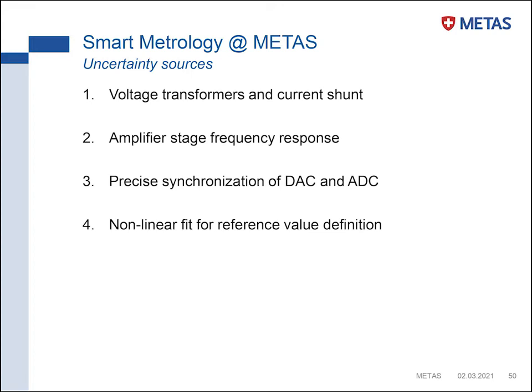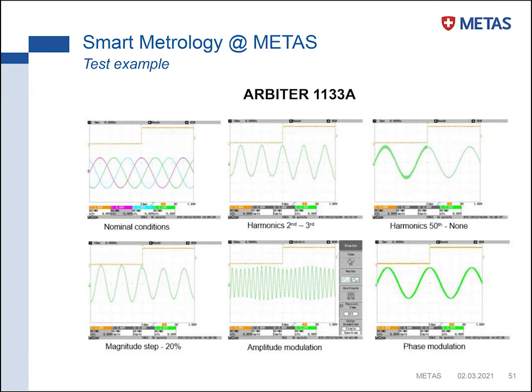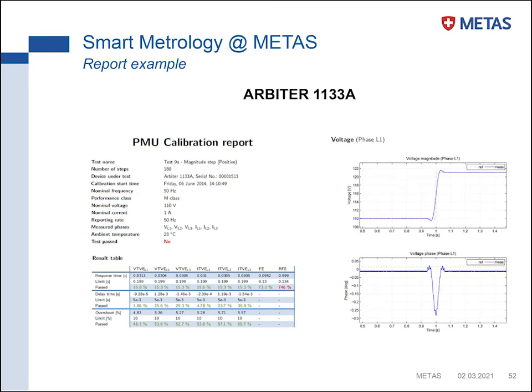This is an example of a test on our PMU here in the lab. And you can see how we are able to reproduce not only purely nominal conditions, but also distorted and dynamic conditions. And we are able to provide a calibration report where we check the error for each channel of the PMU. Here I'm showing an amplitude step where we check the response time I talked to you about before, the delay, and so on. And we can assess the performance of a PMU directly on a very flexible architecture that allows us to reproduce different test conditions, also outside the standard ones.